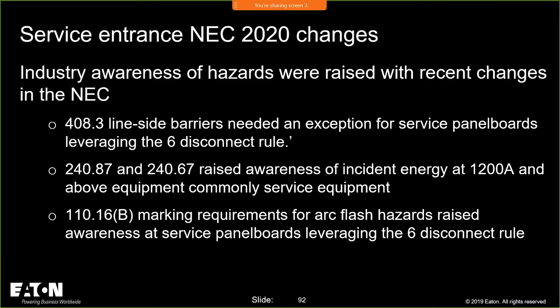240.87 and 240.67 also. So they said, look, we're taking this service equipment and we are going to put arc reduction for 1,200 amps and above, but I can have this 1,200 amp panel board with 6 breakers in it, and I'm staring at an energized bus, and there's nothing I can do about it. I can't put an arc reduction switch in there because I have no main overcurrent protective device.